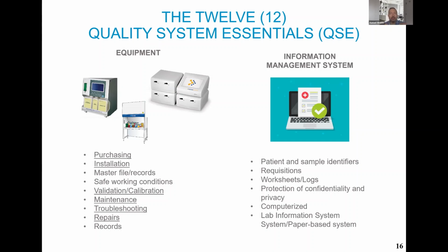But also we have something called routine maintenance. Routine maintenance can be done daily, weekly, monthly, as necessary, depending on what instrument we are running, depending on what recommendations we have from the manufacturer, but we must document. This is one of the pieces that people are missing. When I do my lab accreditations, I notice that a lot of people say, yes, we did the lab maintenance, we maintained the instrument, we primed the instrument, we did the shutdown. And when I ask, can I see it? Can I see the evidence? So a lot of the places we don't keep records. We must keep the records. This is one of the key components, because we must prove that what we're saying is done, right? So let's keep that in mind.